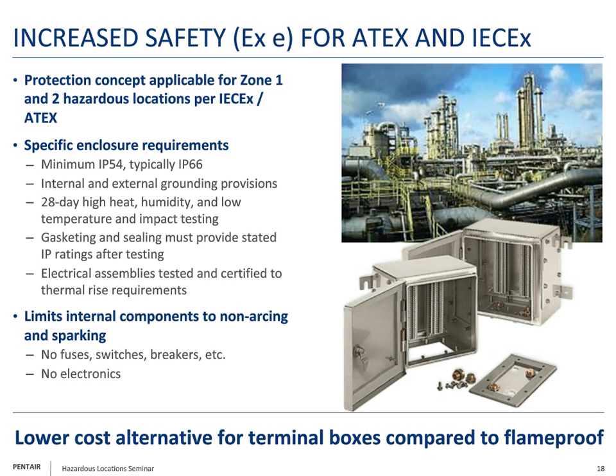But you want to test this assembly with power applied over its broad ambient temperature range to make sure that the enclosure can't get to a high enough temperature that could cause an ignition. So it goes through a pretty rigorous testing profile to make sure that it fits the application and keeps the environment safe. It's a lower cost alternative for terminal boxes when we compare them to FLAMEPROOF. Again, you're using what looks like an IP66 enclosure with some special features. It's a little lower cost than FLAMEPROOF enclosures.